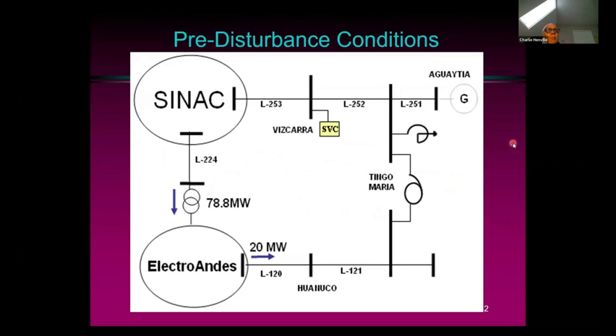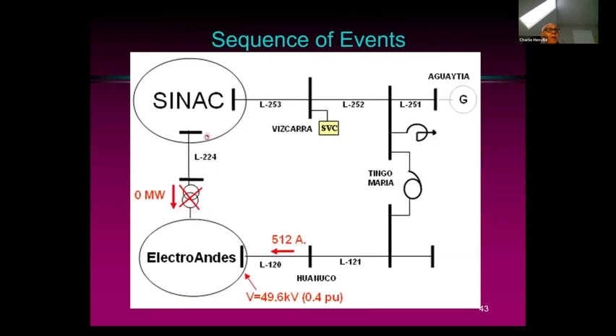This is a case from Peru, which I like to show because it's a real life example of a PV curve that I showed you at the beginning, of the power being delivered can increase and then be reduced. So in this case, what happened was this transformer tripped offline suddenly, and the power that was going that way had to go this long way around like this, and the voltage started dropping, and eventually the protection at this end of the transmission line tripped offline.